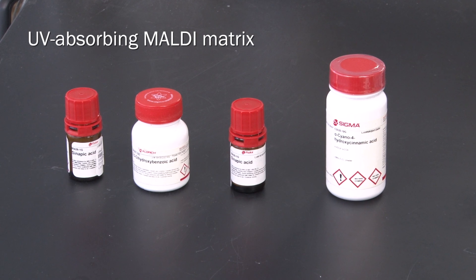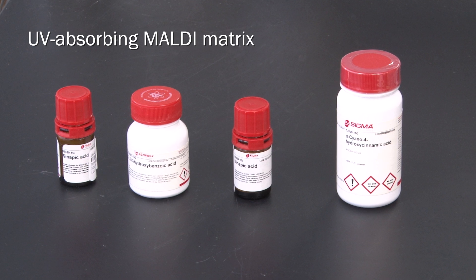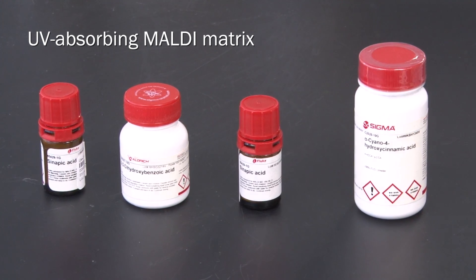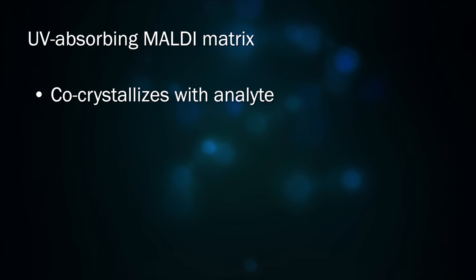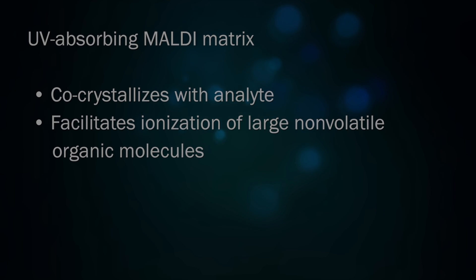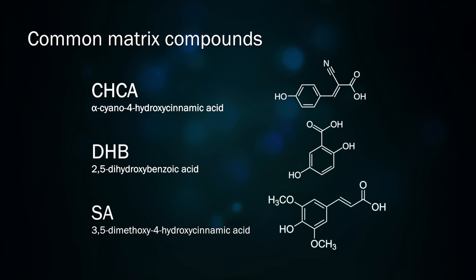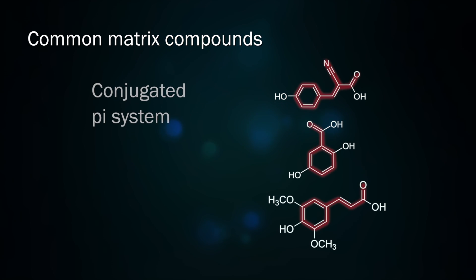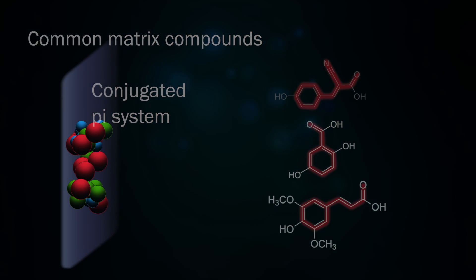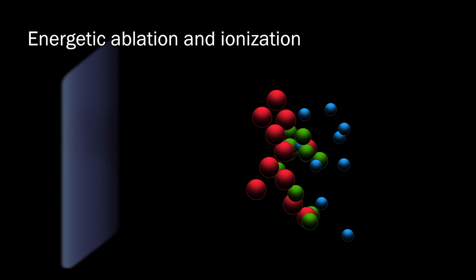One defining characteristic of MALDI-TOF mass spectrometry is the use of a UV-absorbing matrix which co-crystallizes with the analyte on the target plate and facilitates ionization of large, non-volatile organic molecules. There are many substances that are commonly used as a matrix, but they tend to be moderately small organic molecules with a conjugated pi system that absorbs UV light. This allows the energetically excited matrix molecules to physically ablate from the surface of the target, carrying the analyte molecules into the gas phase along with them.